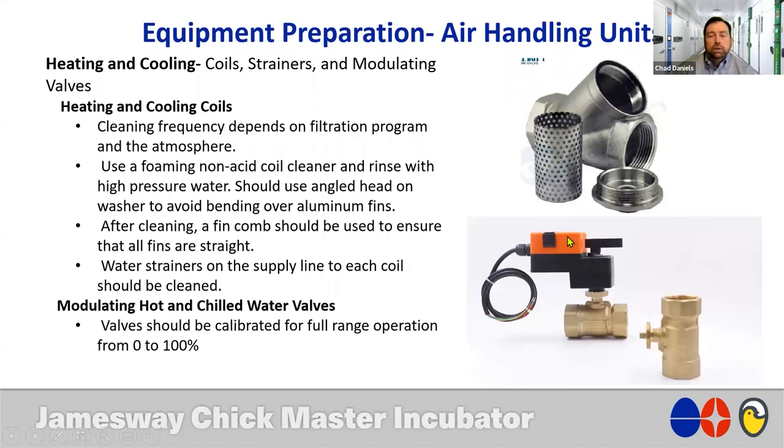This is an example of one of those types of valves. It's kind of two parts. You have the valve body itself, and then you have an actuator. And the electric actuator is what controls flow rate from 0 to 100%. And so in any system where you have modulating control on that flow, it's very critical to make sure that those are calibrated where zero is zero and 100% gives you full flow.